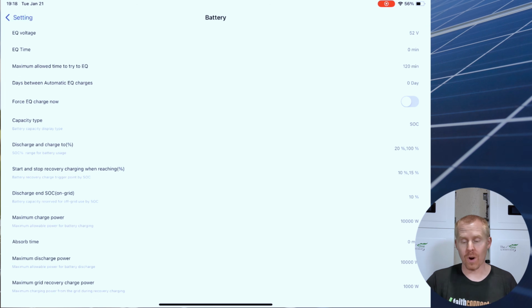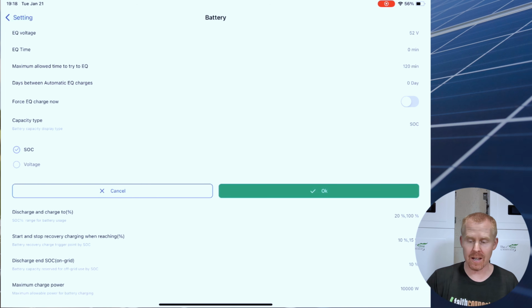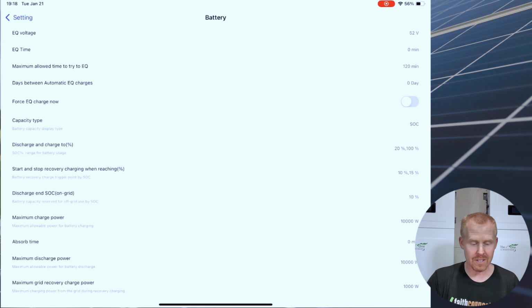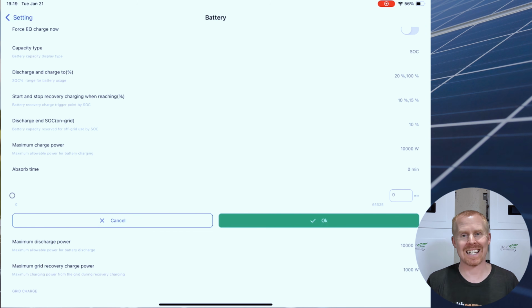The inverter will try and track state of charge. It's not going to be nearly as accurate trying to do it with lead acid batteries, but it's going to try and do that if you have it set to state of charge, or you can set it to voltage. You can see a lot of the same start and stop options, but lead acid batteries do give you the ability to set the absorption time. It's a minute time frame. It looks like you can set it from anywhere from 0 to 65,535 minutes. I don't know why you would ever want to absorb that long, but hey, you can.